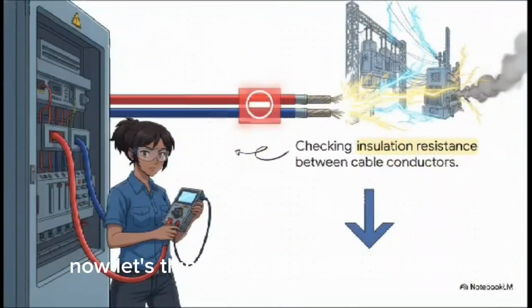Now let's think about a common scenario, testing high voltage cables. When you're checking the insulation resistance between cable conductors, you have to remember to completely disconnect the opposite end of the cable first. If you leave that other end connected to the grid, you are going to get massive errors from electricity leaking into other equipment further down the line. It'll completely ruin your test results.